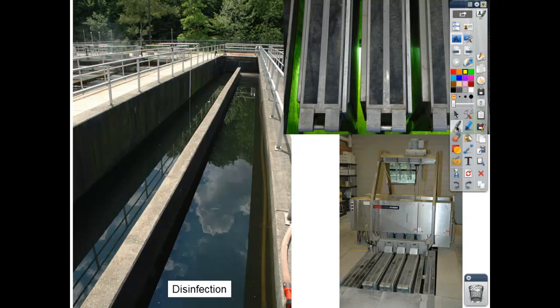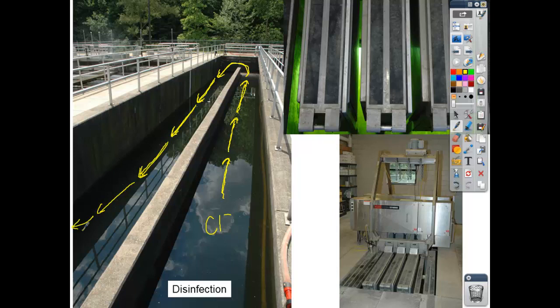The most popular and the cheapest way to do disinfection is to add chlorine to the water and then allow that chlorine to do its work. So they have what's called contact time. I think the standard is 15 minutes of contact time. So as this water travels through this maze, there's 15 minutes. It takes the water 15 minutes to get through this maze, and all the while the chlorine is having contact time with the water and any lasting bacteria before it's going to go out into the nearby creek or stream. So you need that 15 minutes of contact time to kill any lasting bacteria or pathogens that are in there.